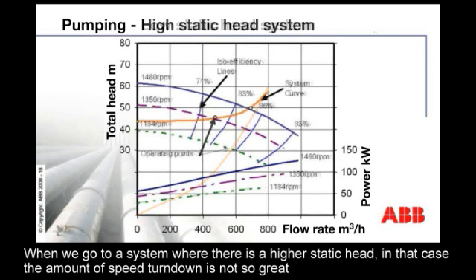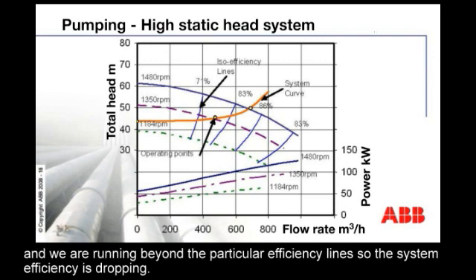When we go to a system where there's a higher static head, the amount of speed turn-down is not so great, and we're running beyond the particular efficiency lines, so the system efficiency is dropping.